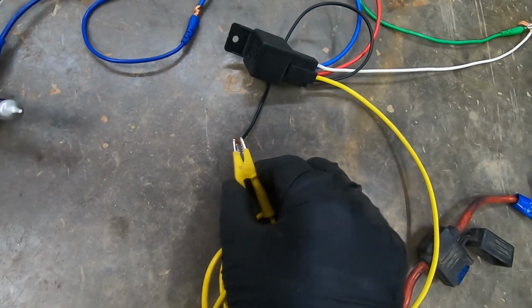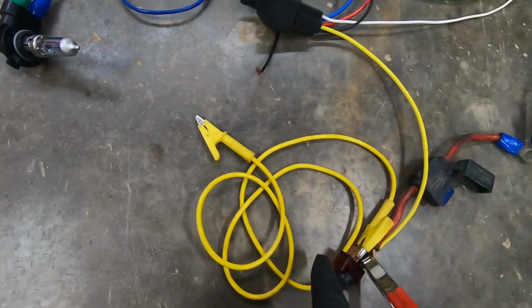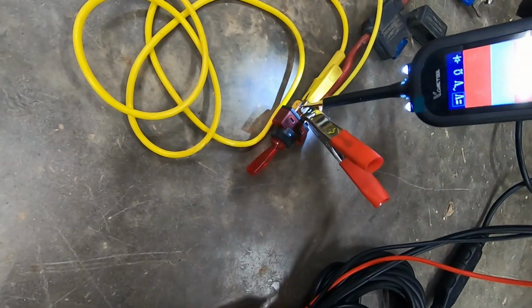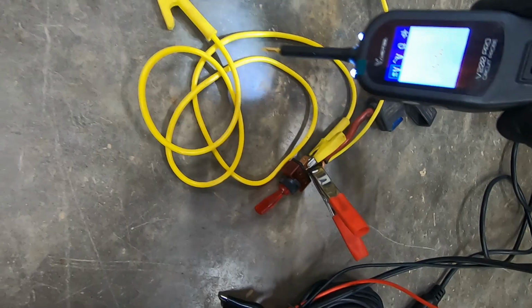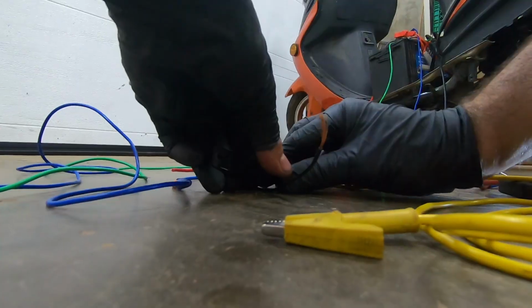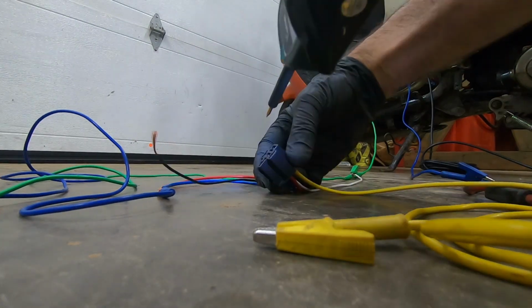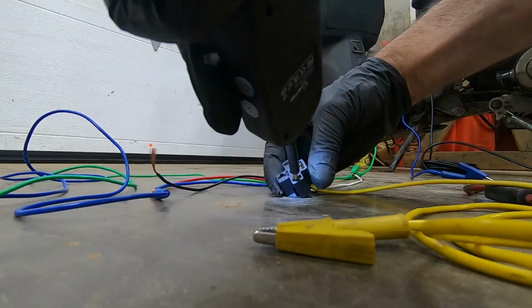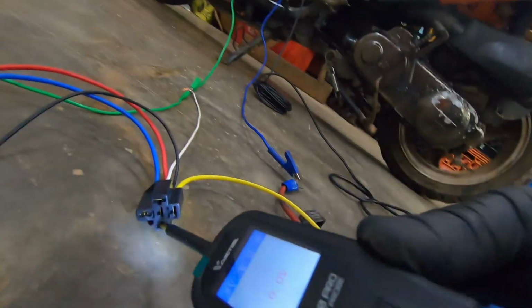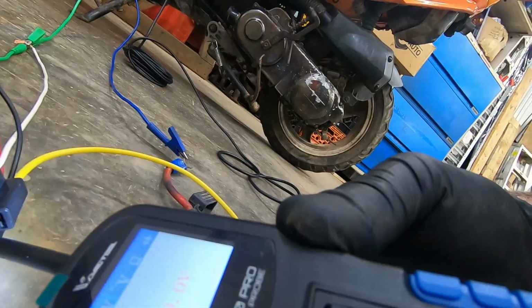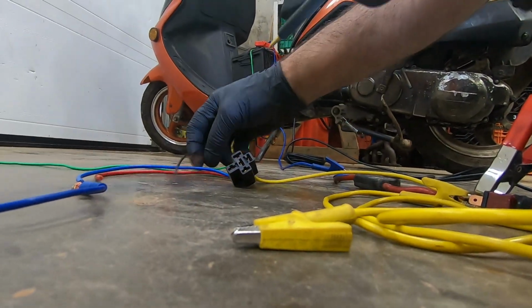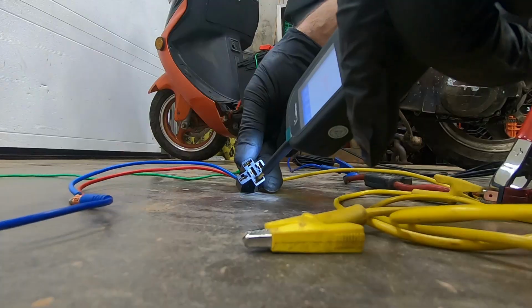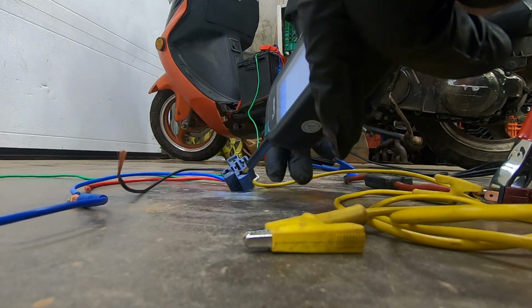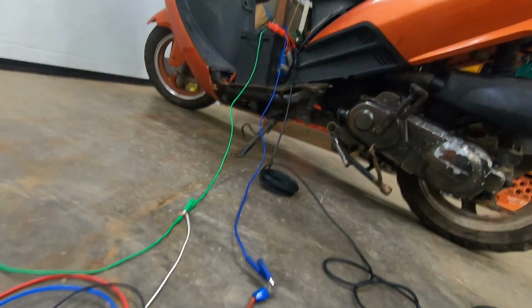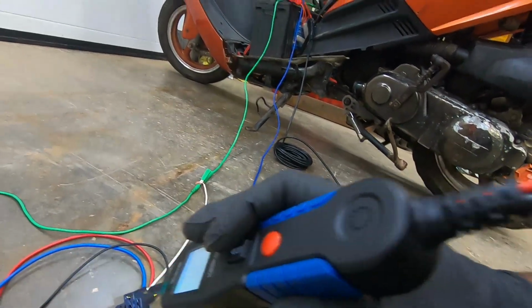What if we break the wires between the switch and the relay? Let's turn the switch on. We look at the output of the switch, there's 12 volts there. If we take the relay out of the circuit so we can test the input to the relay, there should be 12 volts on that black wire, but there's not. That's because there's a broken wire. So if you check the relay input and find 0 volts, but the switch output is giving you 12 volts, you need to chase a broken wire between the switch and the relay.